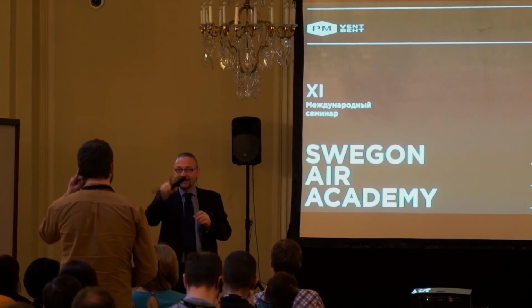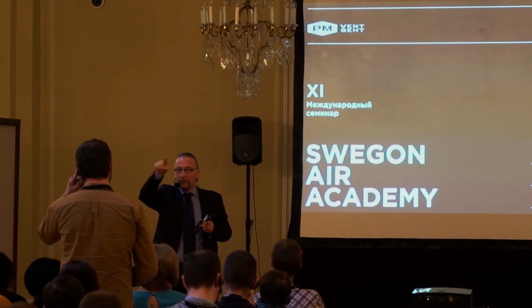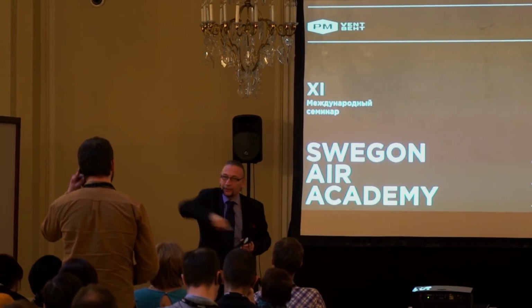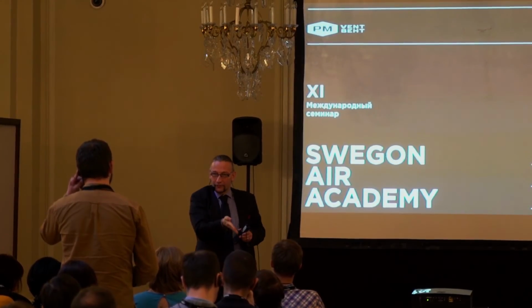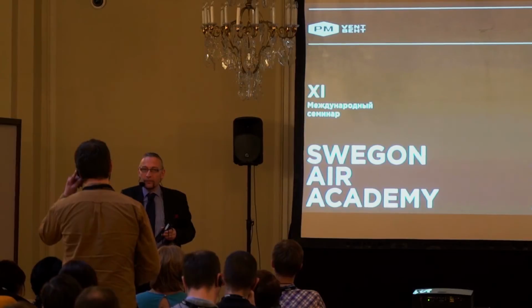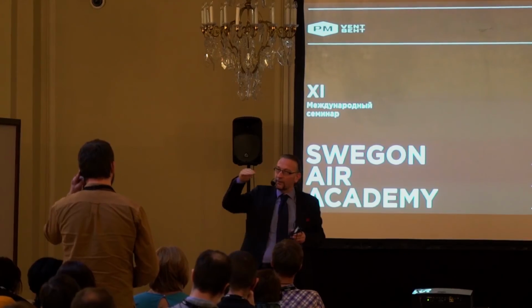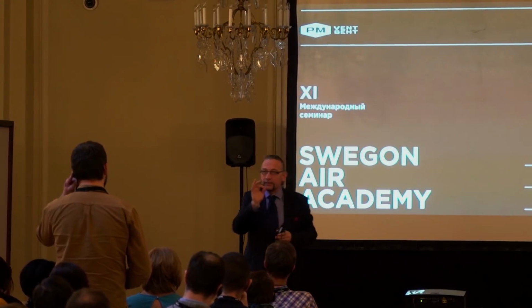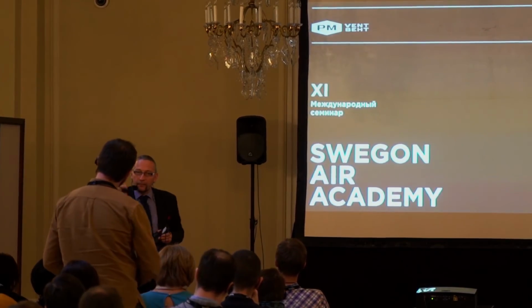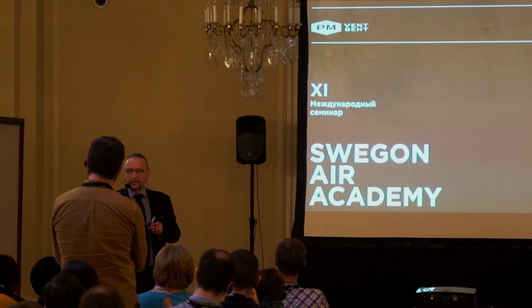SFP goes down. If you imagine you have a duct, and you need a certain amount of air going through the duct, and you reduce the air volume to 50%, the amount of energy is 8 times less. It's to the power of 3, because pressure goes down in square, and air volume goes down by half. You understand that? So reducing air volume and pressure at the same time is not only half the energy bill, it's 1/8 of the energy bill. It's only 15% left. So the money goes down very, very quickly. So that's why it's very important to work with a low pressure and variable air volume. Is that an answer to your question?